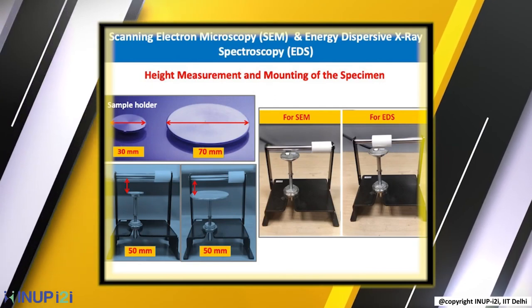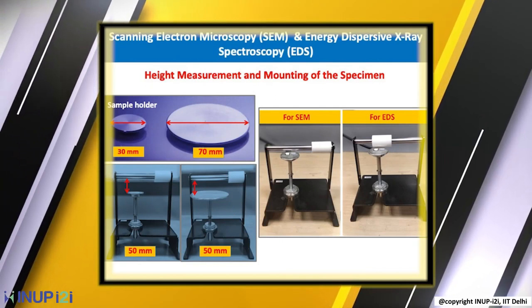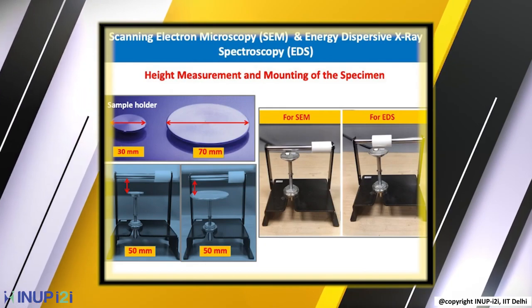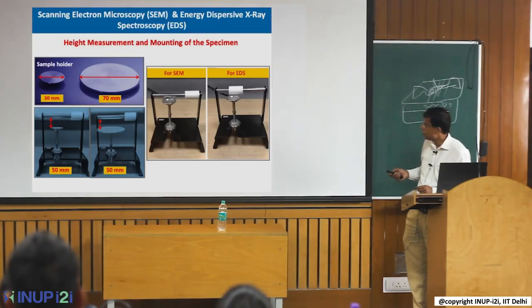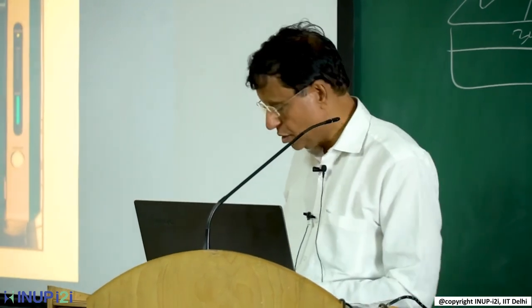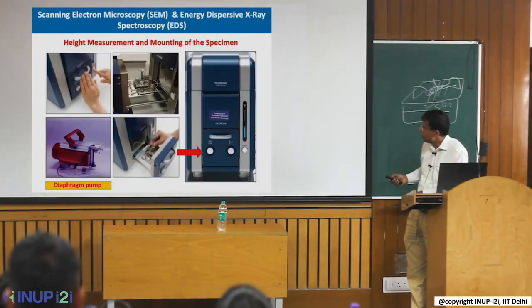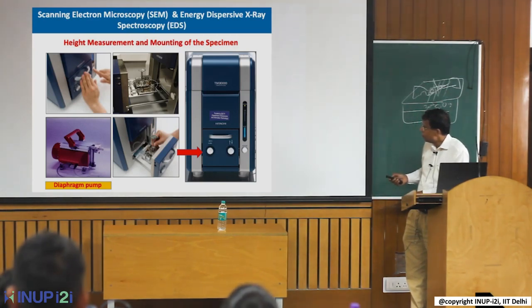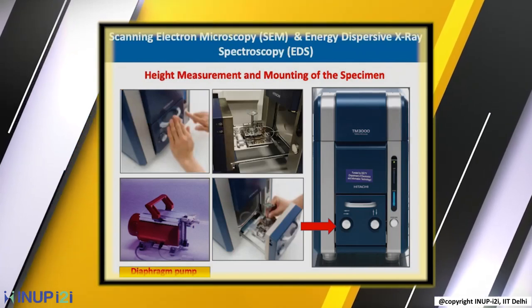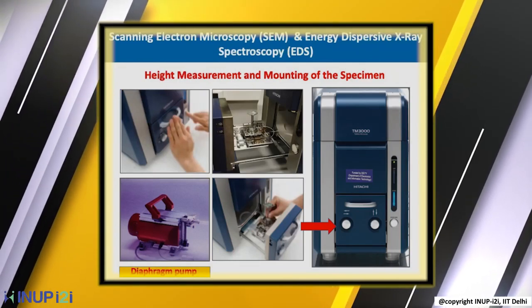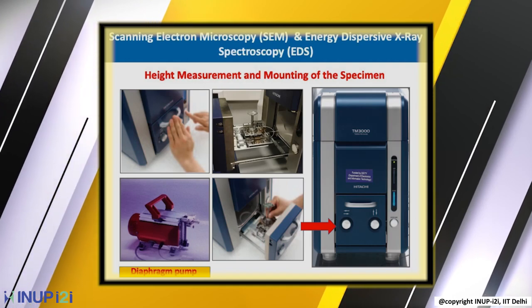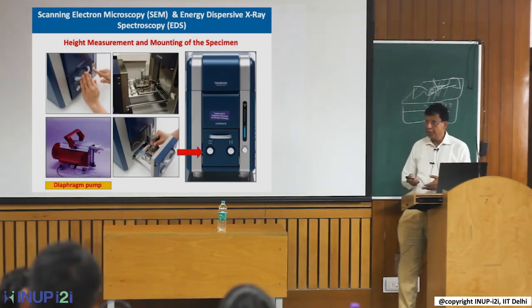These are photographs showing the SEM and how samples are placed. For EDS you keep the detector slightly farther; for SEM imaging you can go nearer. The sample is placed on the stage, the chamber is closed, the pump is turned on, and only when vacuum is created is the gun switched on and image acquisition begins.